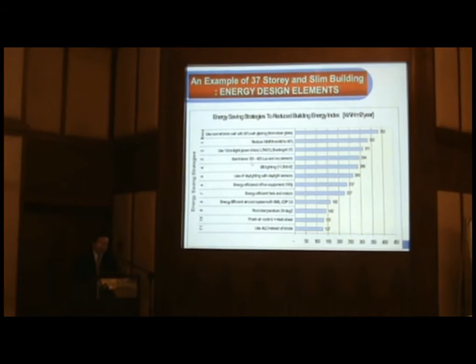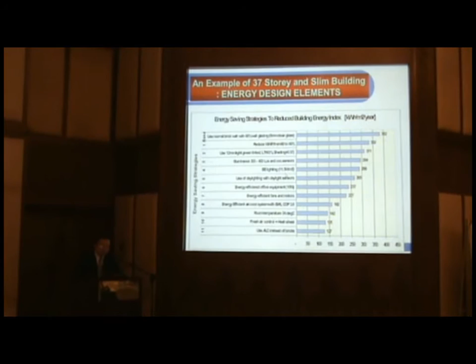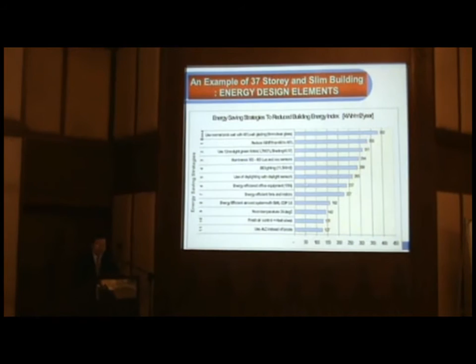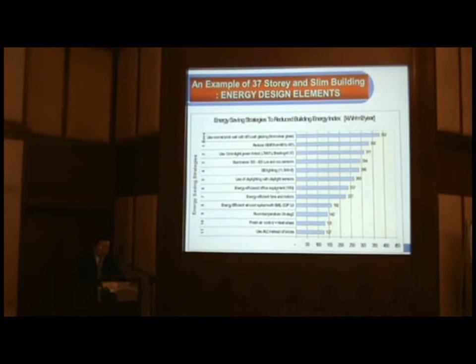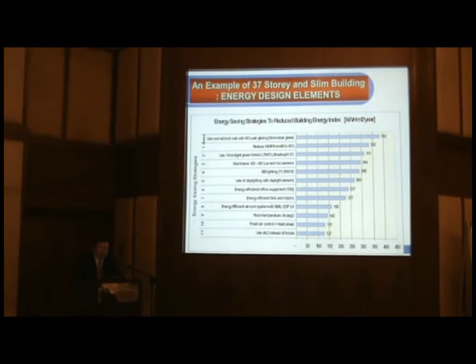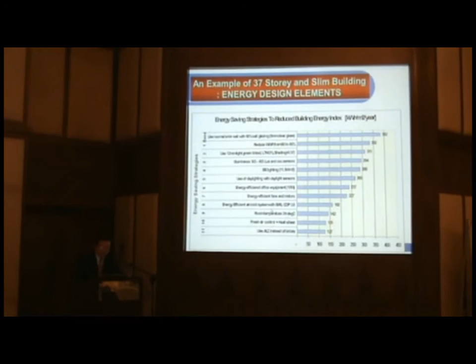So some reductions. For use of the MS1525 lighting luminance in the office plus occupancy sensor, meaning nobody there, it will turn off. Energy efficient lighting design, using T5 for example instead of just fluorescent. And then some areas have a penetration of daylight with the sensor, you can see the reductions. Even the office equipment, 10 watt per square meter. High efficient motor, energy efficient air distribution, no losses for the ventilation. Energy efficient aircon system with building automation system, the coefficient of performance at 3.8 instead of lower than that. So huge reduction.